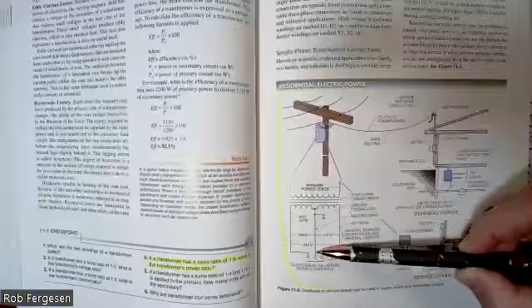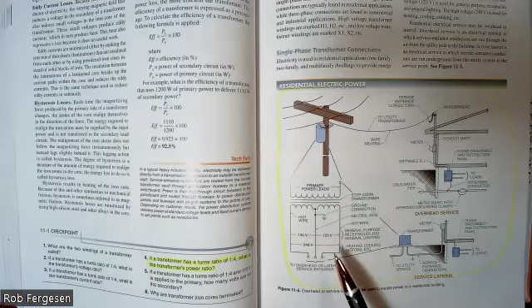You can take either one of your legs and use it with the white wire to create 120 volts, and you try to balance it so you're not always using one leg or the other. In your circuit breaker box, you try to distribute your load so you're using a little from each leg of this transformer. That's how single phase power works.